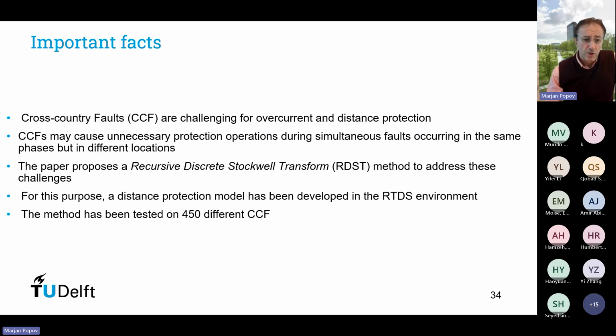Those who work with power system protection are aware that cross-country faults are one of the most challenging contingencies for overcurrent and distance protection. Cross-country faults may cause unnecessary protection operation during simultaneous fault occurrence. For instance, when we have, on one line or on different lines, at the same time different or the same types of faults, protection can maloperate or may not operate.